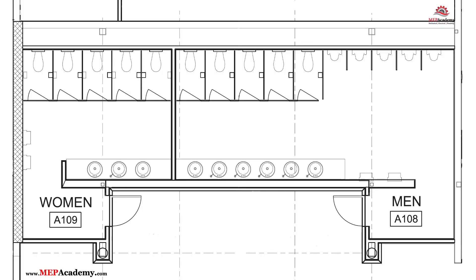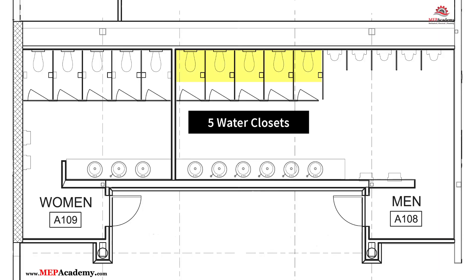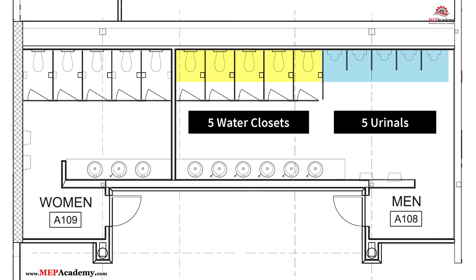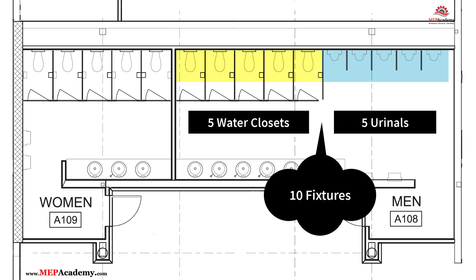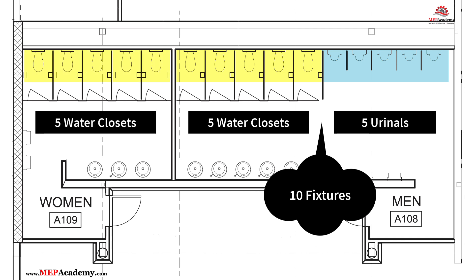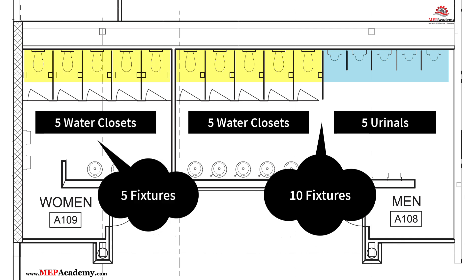Now let's size the fans for a real-world example. Men's public restroom: 5 water closets and 5 urinals, for a total of 10 fixtures. Women's public restroom: 5 water closets, for a total of 5 fixtures.